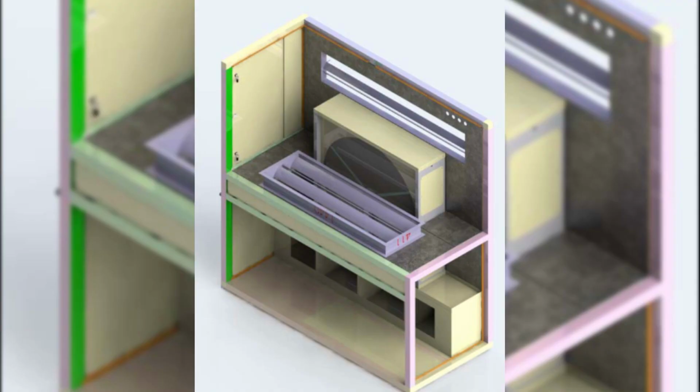7. If a public assembly space can be divided into independent subspaces, multiple zone VAV heat pump or dual-temperature air handling units must be used instead of single-zone VAV units. Each subdivided space needs its own VAV box and temperature sensor. 8. Energy recovery wheel and demand-controlled ventilation are mandatory design features for units serving public assembly spaces, as indicated by SCA standards and building codes like ASHRAE 90.1 2016 and the 2020 NYC ECC.